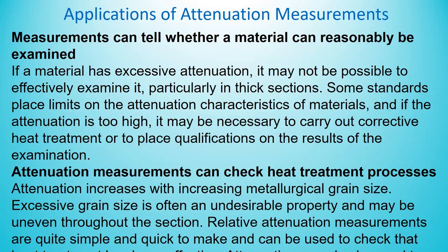Application of attenuation measurement. Measurement can tell whether a material can reasonably be examined. If the material has excessive attenuation, it may not be possible to effectively examine it, particularly in thick sections. Some standards place limits on the attenuation characteristics of material, and if the attenuation is too high, it may be necessary to carry out corrective heat treatment or to place qualifications on the result of the examination.